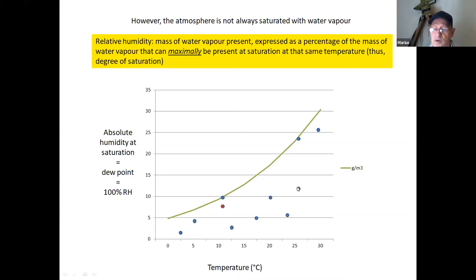Likewise, on the right, at 25 Celsius, saturation is about 24 grams per cubic meter. This specific sample down there is about 12 grams. In other words, we are half saturated, so we had 50% relative humidity. So that's what the relative humidity tells us. It doesn't tell us how much moisture is in the air. All it tells us is the degree of saturation of the air with moisture. So if it's 50% relative humidity, it means the air has the capacity to hold twice as much moisture as is currently present in the air. In other words, this sample can hold twice as much moisture as what is present in the air at that specific time.